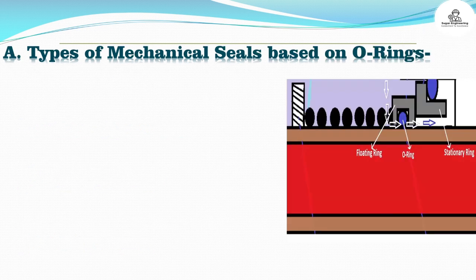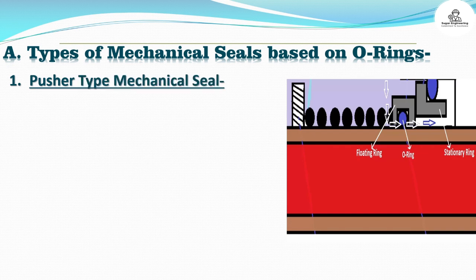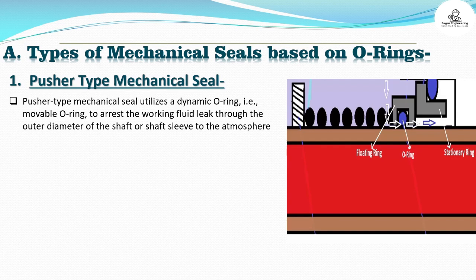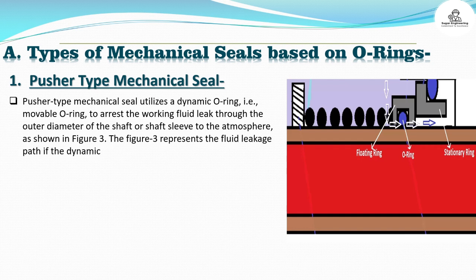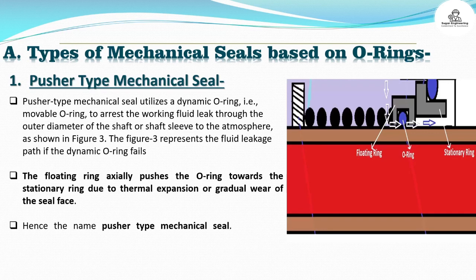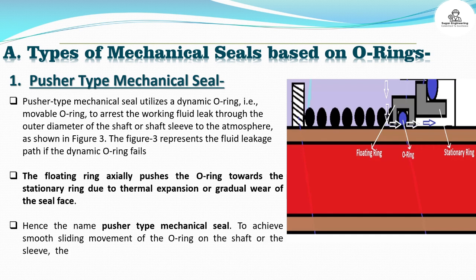Types of mechanical seals based on O-rings. Pusher type mechanical seal: A pusher type mechanical seal utilizes a dynamic O-ring — i.e., a movable O-ring — to arrest the working fluid leak through the outer diameter of the shaft or shaft sleeve to the atmosphere, as shown in Figure 3. The floating ring axially pushes the O-ring towards the stationary ring due to thermal expansion or gradual wear of the seal face. Hence the name pusher type mechanical seal. To achieve smooth sliding movement of the O-ring on the shaft or sleeve, the surface must be very smooth.